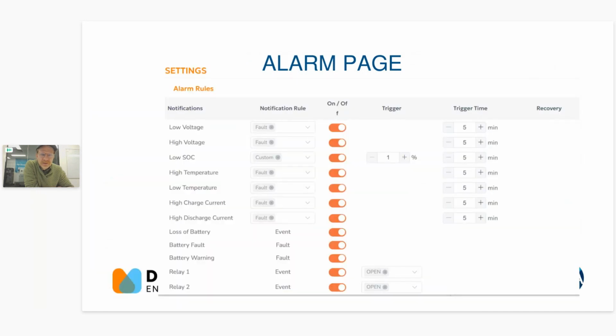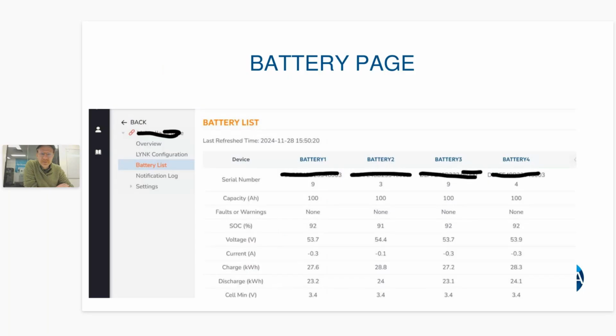But what we're really interested in is detailed alarms. So it has an alarm page here, which will give you high and low voltage, state of charge, temperature, all of these alarms that can get sent to your email address for each individual battery. And you can set the trigger time as well, there's a bit of nuance there.